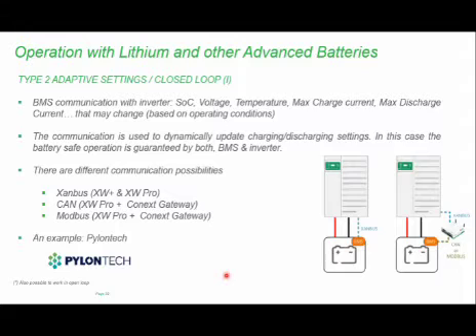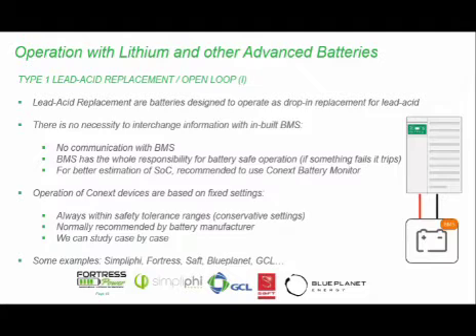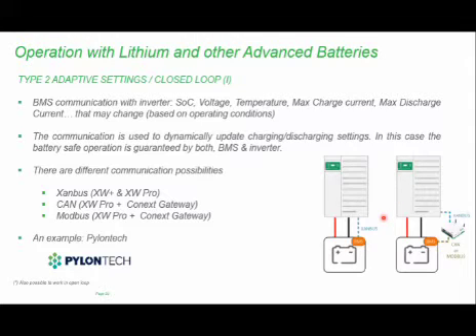Then in comes closed loop compatibility. If you take note of the pictures I showed you, in the previous one, the BMS for this battery is not communicating with the inverter. Now we move to closed loop compatibility. Here, the BMS is connected to the inverter. It's no longer just your positive and negative lines from your inverter to your battery, you have your communication line also. Sometimes our inverter speaks Xanbus, this is why you're seeing Xanbus here, but there are also different communication lines for BMS of batteries, like Modbus or CAN bus. In this case of PYLONTECH, we communicate with it using CAN bus.